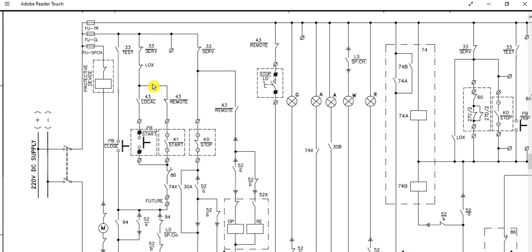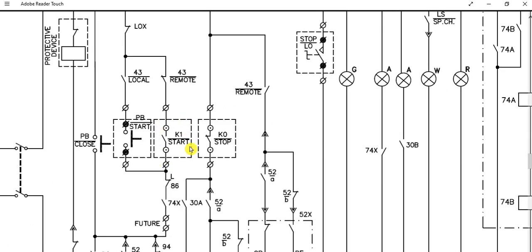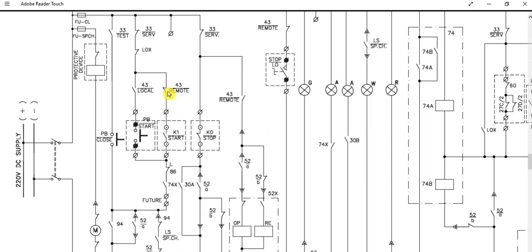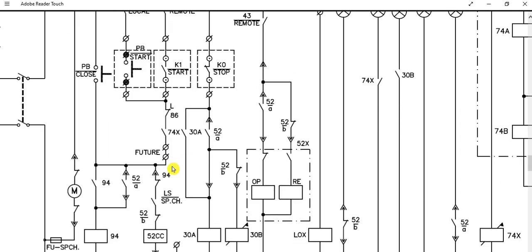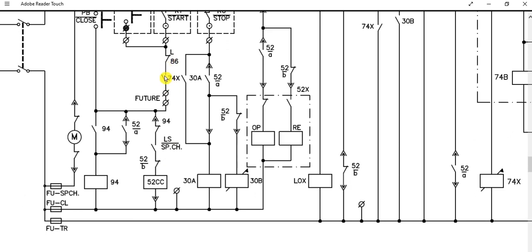If the control switch position is in remote, this path is followed. K1 start is the remote operation command coming from DCS or PLC to close the circuit breaker. If you issue the close command K1 via remote, and the 86 relay is not operated and the 74X trip circuit supervision relay is OK, then it will follow this path and energize the 52CC closing coil, and the breaker will be closed.